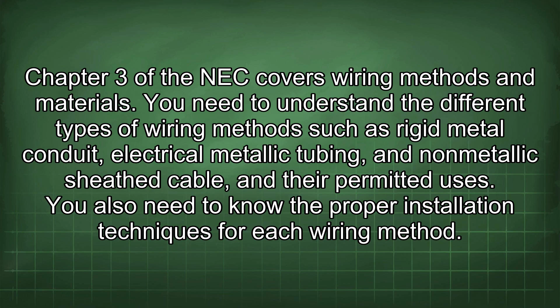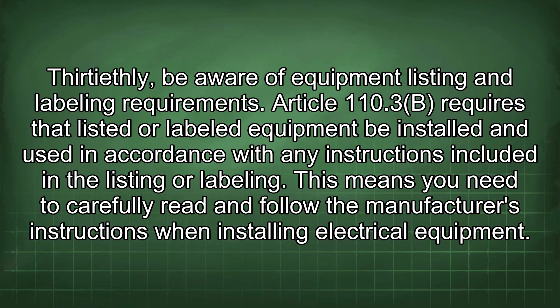30th, be aware of equipment listing and labeling requirements. Article 110.3(B) requires that listed or labeled equipment be installed and used in accordance with any instructions included in the listing or labeling. This means you need to carefully read and follow the manufacturer's instructions when installing electrical equipment.